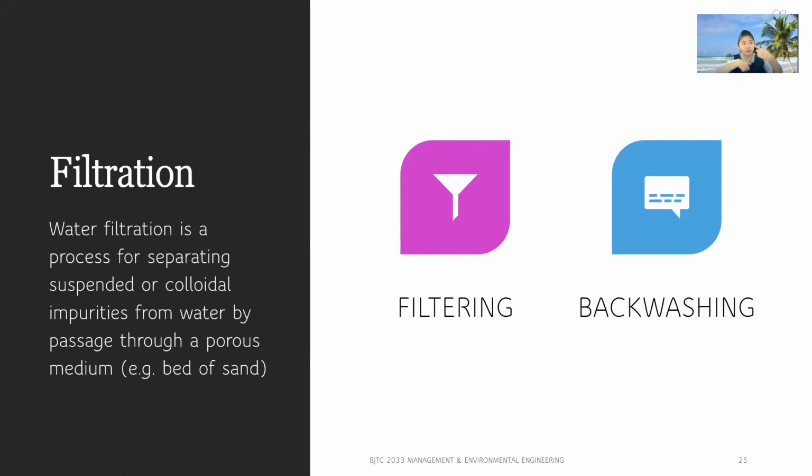So we wash all the sand that we have inside to make sure that it is not saturated. Otherwise, once you filter for too long, it will close the surface of the porous media. So now we have to backwash it.